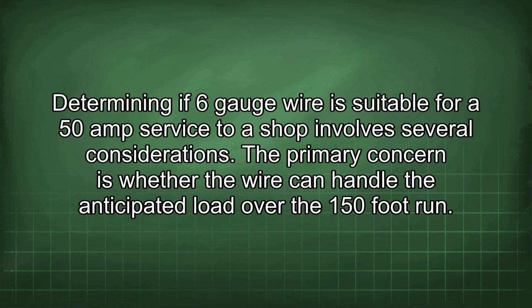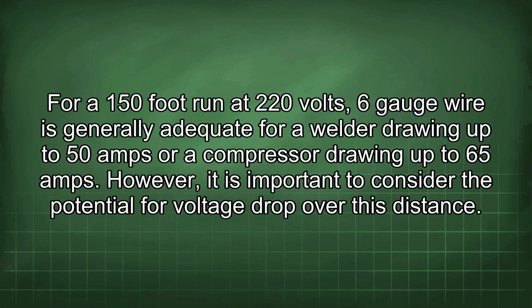Determining if 6-gauge wire is suitable for a 50-amp service to a shop involves several considerations. The primary concern is whether the wire can handle the anticipated load over the 150-foot run. For a 150-foot run at 220 volts, 6-gauge wire is generally adequate for a welder drawing up to 50 amps or a compressor drawing up to 65 amps.